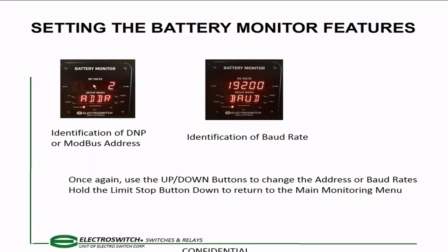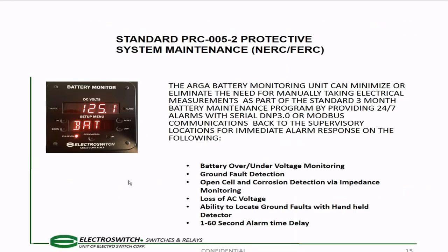And if you're using DNP or Modbus, you want to put in your address and whatever baud rate. As I said at the beginning, this unit is not PRC005-2 compliant because we don't monitor individual cell voltages. We monitor the battery strength. PRC005-2 says you have to monitor individual cell volts, have temperature monitoring, and 24/7 output. We would get 24/7 output by tying it into a data storage system, but we don't have a data storage system associated with ours. When it ties into your battery monitoring system, you bring in individual cell voltage, temperature monitoring, and all the data storage. Now, with impedance monitoring and the ground detection, you have a complete system addressing PRC005-2.